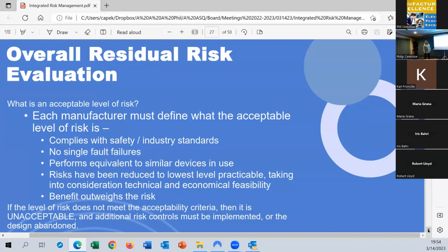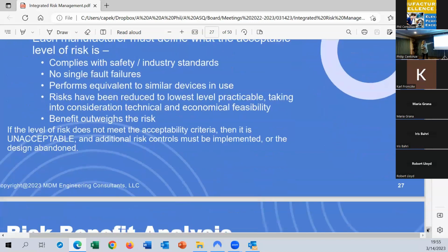And lastly, the benefit has to outweigh the risk. So if there's a way that the patient can get the same benefit with less risk, then the benefits don't outweigh the risk. Right? So we want to do a risk-benefit analysis to ensure that the benefit of using our device outweighs the risk for the patient. And if we have unacceptable risk, then we either apply more controls to make it acceptable, or we abandon the design.